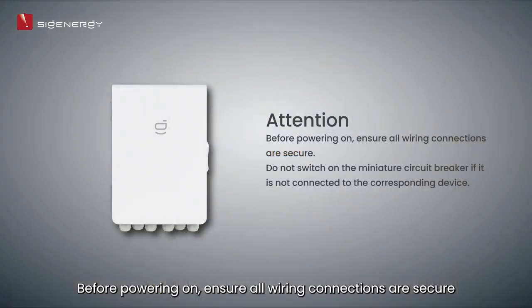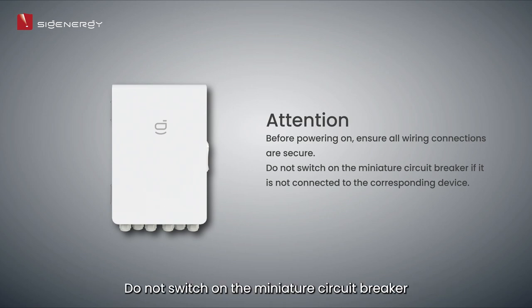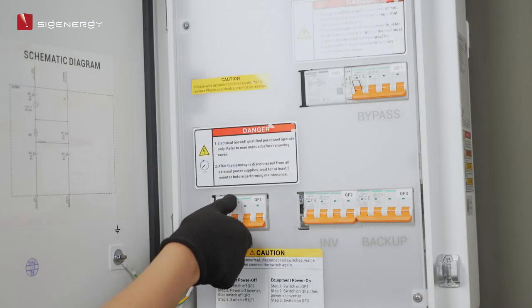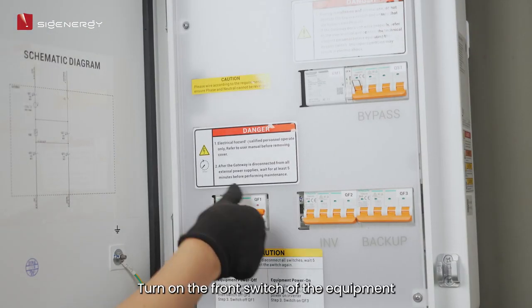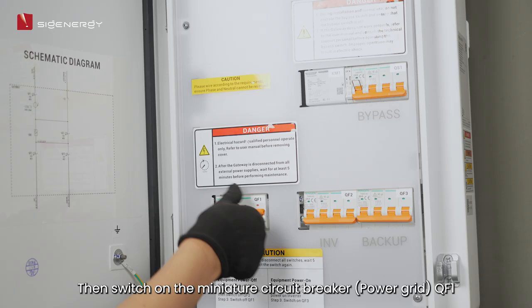Before powering on, ensure all wiring connections are secure. Do not switch on the miniature circuit breaker if it is not connected to the corresponding device. Turn on the front switch of the equipment. Then switch on the miniature circuit breaker, power grid, QF1.